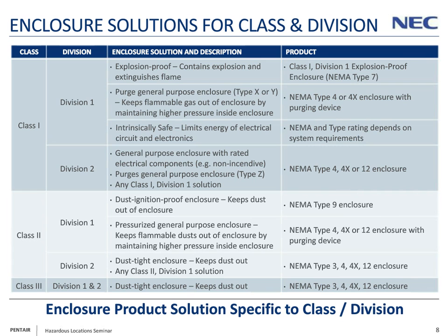Class 1 Division 2, you can use any Class 1 Division 1 solution, and then you have another two options. You could use a NEMA Type 4, 4X, or 12 enclosure with rated electrical components. So the components are actually rated for Division 2 areas. They're non-incendive, they're non-arcing, and we'll explain what that means in a couple of slides here. You can also purge a general purpose enclosure, and that's just called a Type Z purge. Very similar concept to what we talked about already, but you have that option available to you.